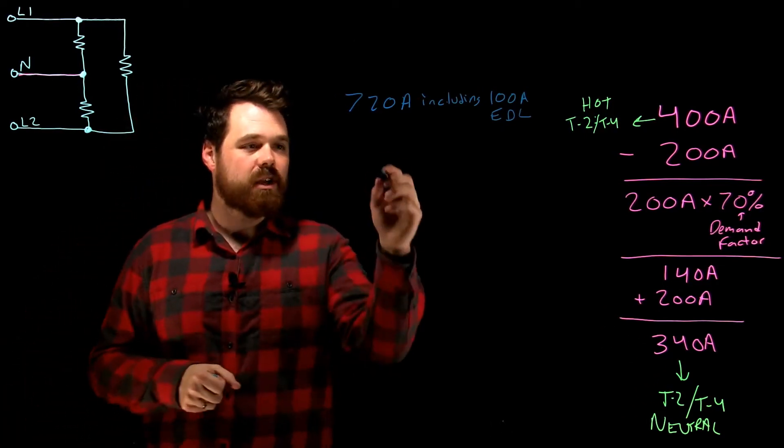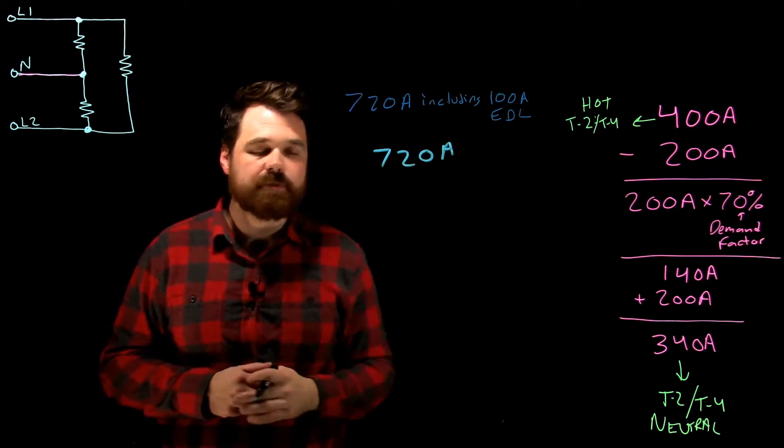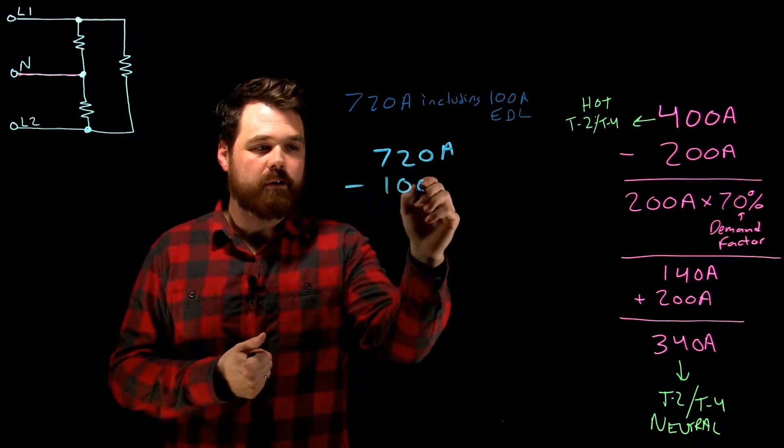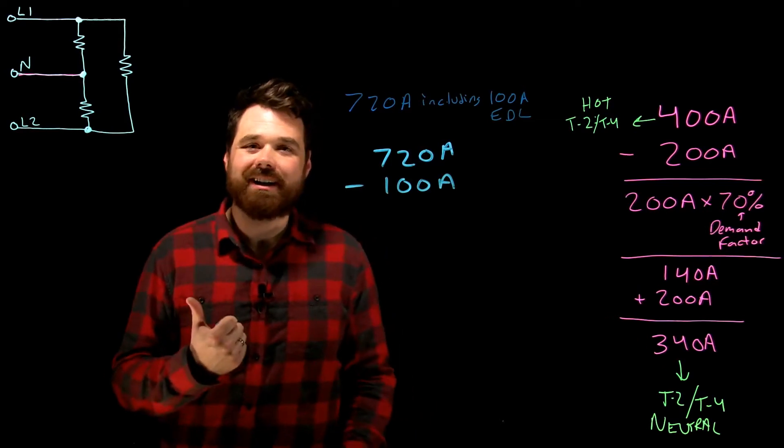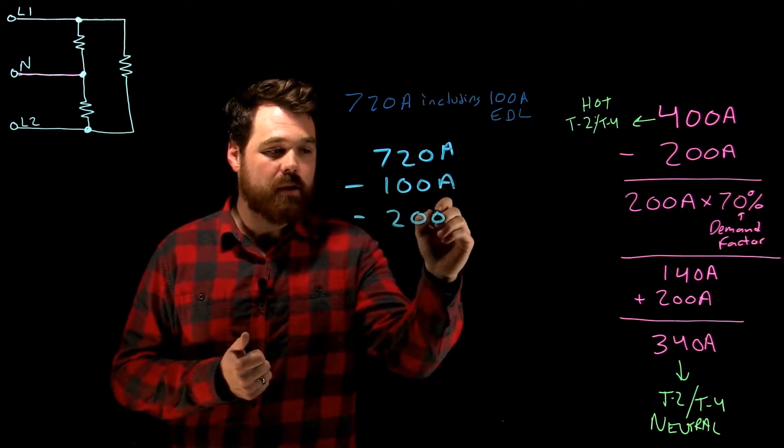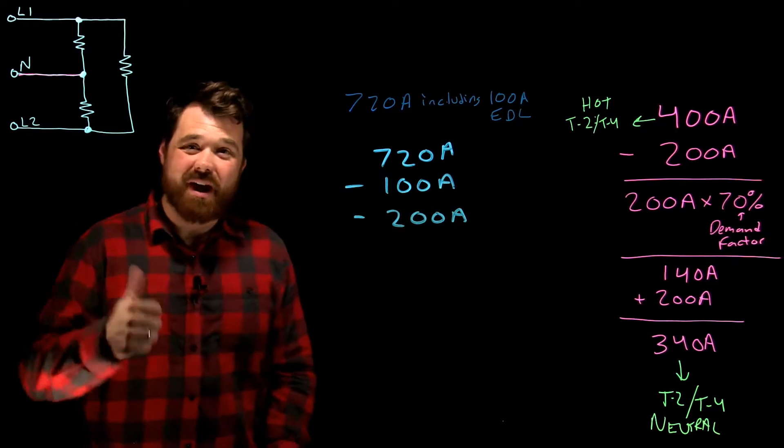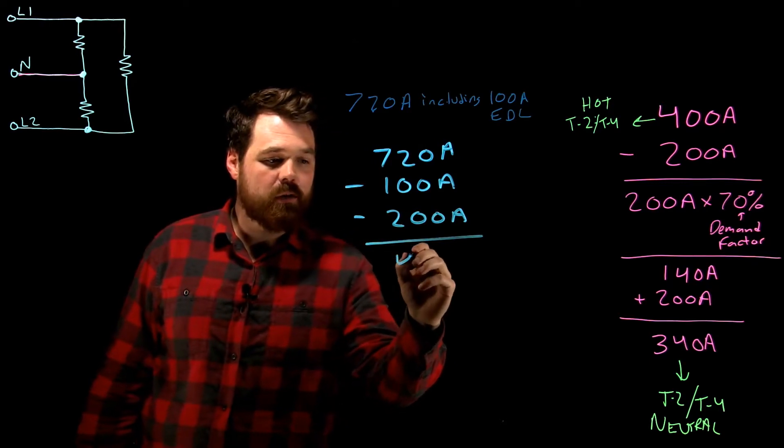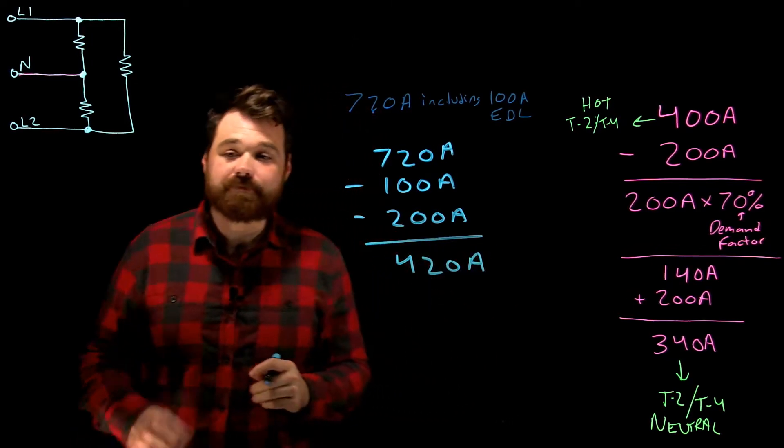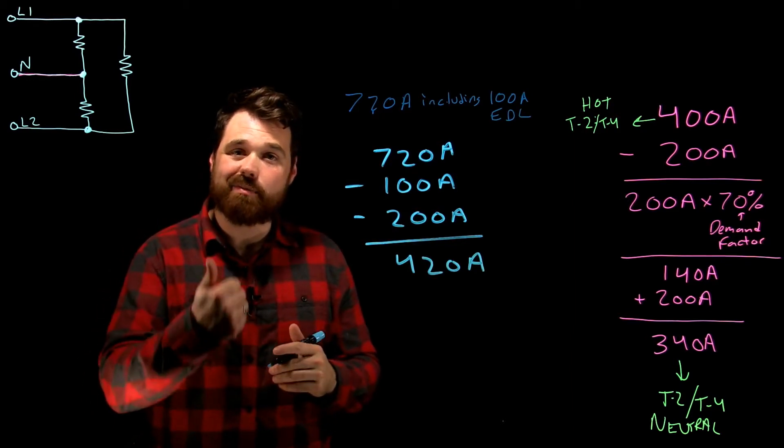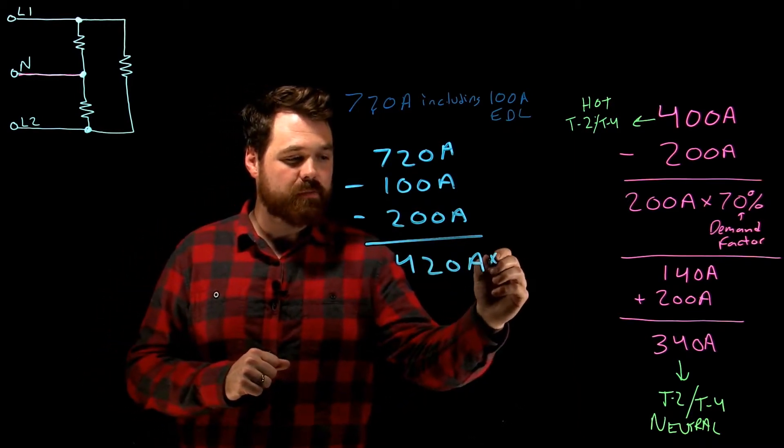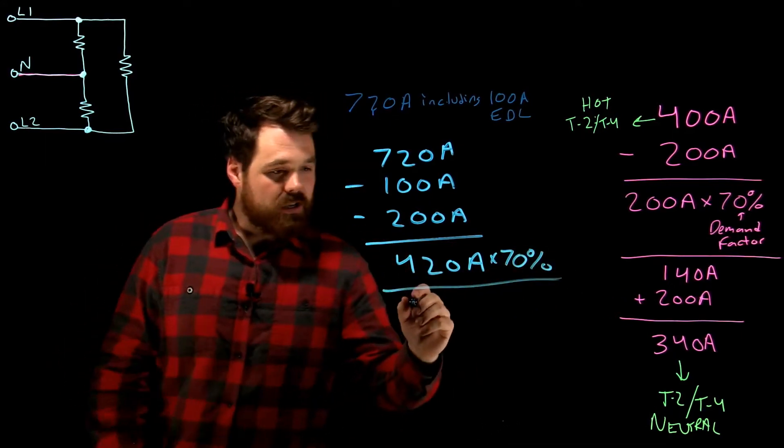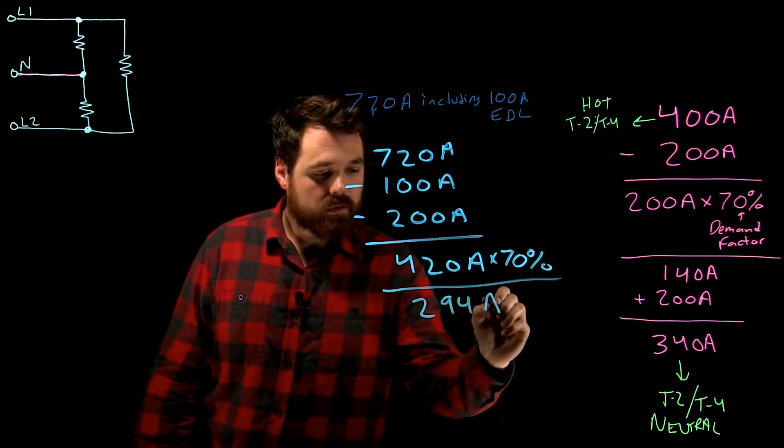So if that was the situation and I had that, what I would have to do is I would take my 720 amps, right? I cannot apply a demand factor to my electric discharge lighting, so I'm going to minus my 100 amps of electric discharge lighting. I'm also going to minus that 200 amps, which I cannot apply a demand factor to. That's going to give me in this case 420 amps. Now this 420 amps is what I can apply a demand factor to. So I'm going to multiply it by 70%, which gives me in this case 294 amps.